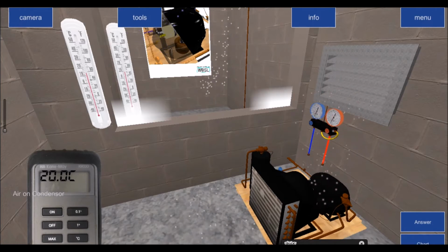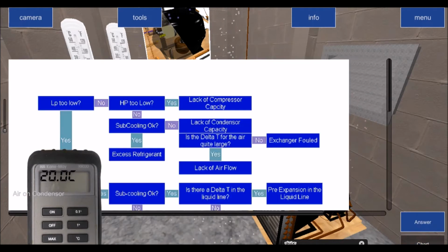So again, what should we be getting? 10 to 20 of a difference is what we're looking for. So with air on of 20, we would add 20. The maximum condensing temperature we're looking for is 40. The minimum condensing temperature is 30, or anywhere in between. So it should be between 10 to 20 of a difference. Condensing temperature should be 10 to 20 degrees higher. In this particular case, it's 25 degrees higher. So then we go back to the chart. Is HP too low? The answer to that question is no. It's too high.